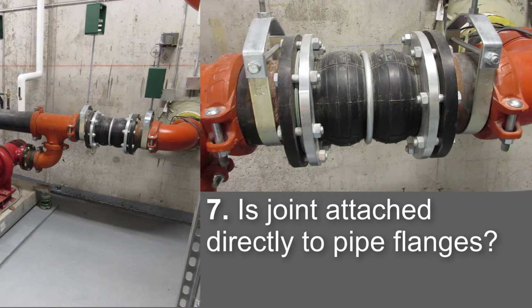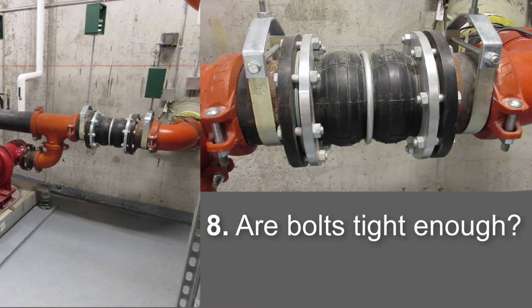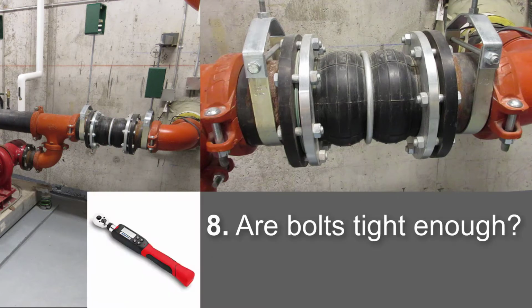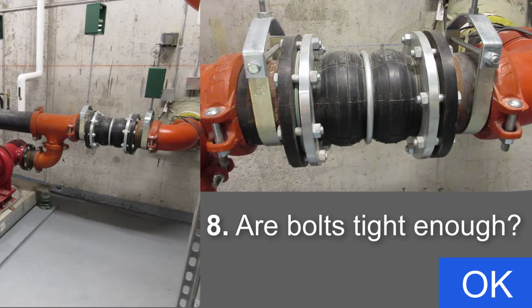Is the expansion joint attached directly to the pipe flanges without any other unflanged component in between? As we can see here, the joint flange is connected directly to the pipe flange, so this is okay. Eighth, are the bolts tight enough? I didn't bring a torque wrench to check, but in some cases it may be appropriate to spot check the flange bolts to ensure the contractor has followed the multi-step process to get the bolts in the correct torque range. These appear to be okay.